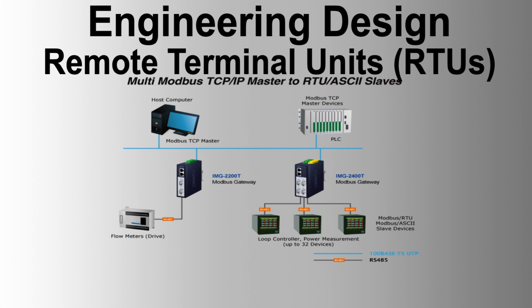Advanced diagnostic information, accessible via the RTU Programming and Configuration Interface program. This includes detailed diagnostics for I/O modules, such as health and presence of each RTU module, current state value of each I/O channel, including power supply I/O data. Processor module diagnostics, scan rate: information on the scan rate of I/O and logic, providing insight into the processing speed and efficiency. Current time and date: ensures synchronization and accurate timestamping of events and data.